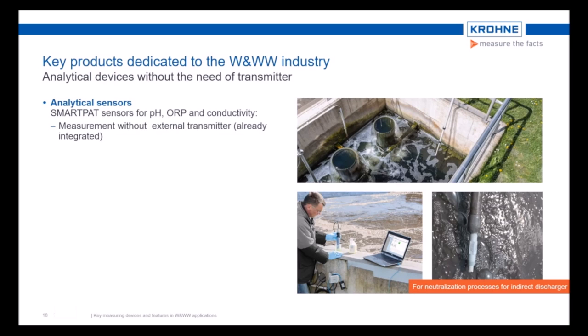Besides the flow measurement, we have of course some more important parameters to measure, such as pH, ORP or conductivity. This can be realized with the so-called SMARTPAT sensors. Those intelligent analytical sensors do not require an external transmitter as others do. The complete transmitter technology is integrated into the sensor head directly. That means the signal is directly converted into a measuring value within the sensor itself, so you will not have any moisture influence, etc.